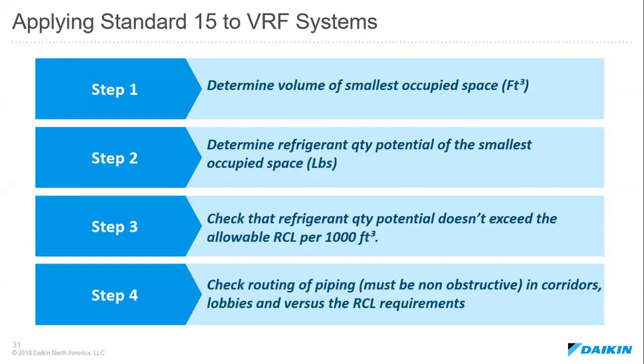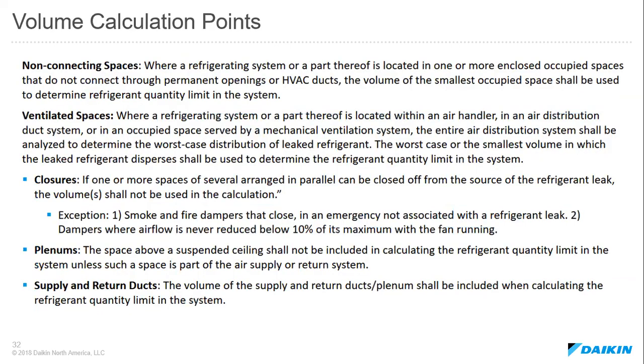Now I'll talk about how ASHRAE Standard 15 can be applied in practice to VRF systems by showing you a few examples. There are 4 steps. Step 1, we want to determine the volume of the smallest occupied space. Step 2, we want to determine the refrigerant quantity potential of the smallest occupied space. Step 3, we want to check that the refrigerant quantity potential does not exceed the allowable concentration level per 1,000 cubic feet. And then step 4, we'll check the routing of piping, which has to be non-obstructive in corridors and lobbies, versus the RCL requirements.